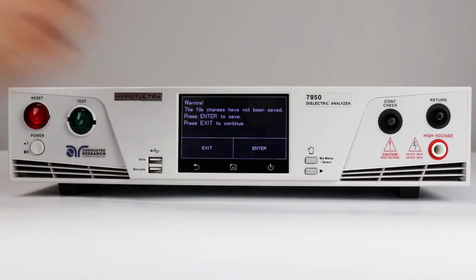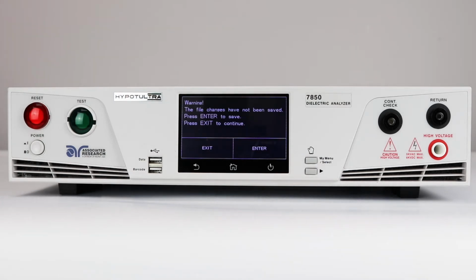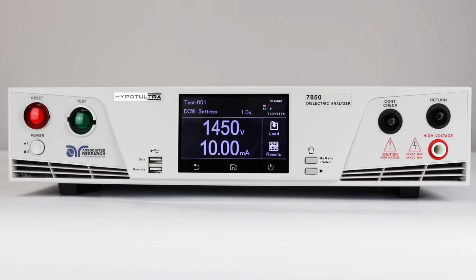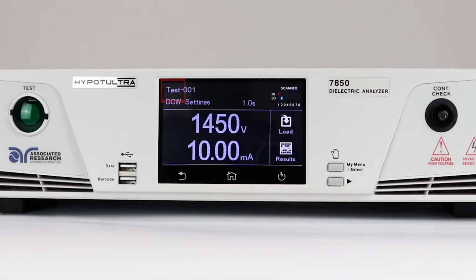You'll be prompted to save your test file changes. Press Enter to confirm. The Perform Test screen displays the following parameters: file name, file number, test type, status indicator, test time, test voltage, leakage limit or resistance limit indicators, and scanner status if the scanner option is installed.